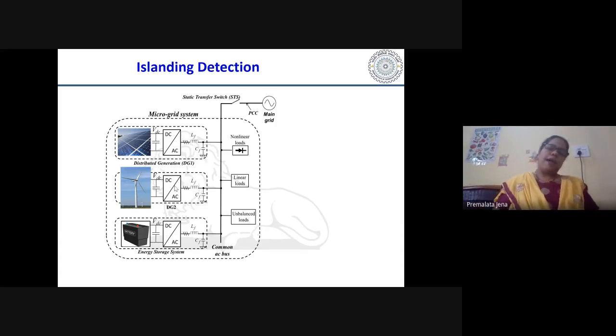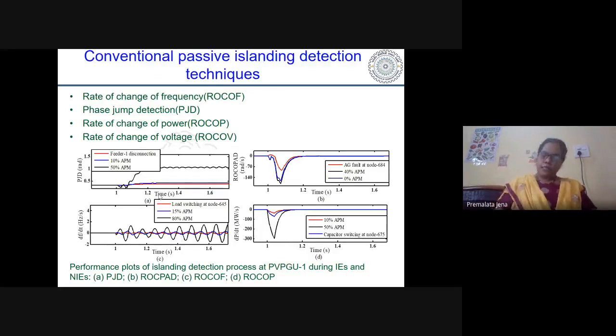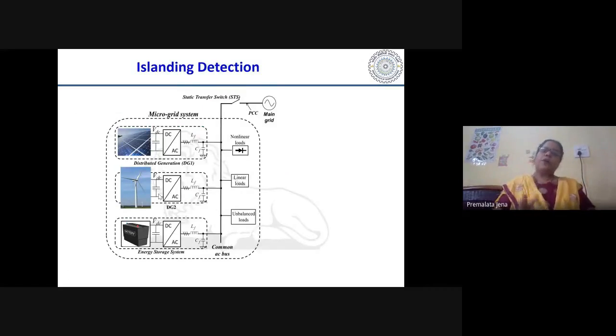So coming back again to our unintentional islanding part, which I started from the beginning. If suppose the grid is off, and if you all remember, I said that in today's date our penetration of renewables is up to 20 to 30%. It should be noted down. If suppose I have 100% load, I am getting 20 to 30% from the renewables. So 70% I am getting from the grid. That means I am getting 70% power from the rest of the grid. So when the grid is off, suddenly 70% power is off, and I am only getting 20-30% power from the renewables. However, my load requirement is 100%.